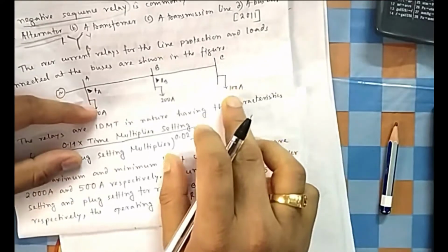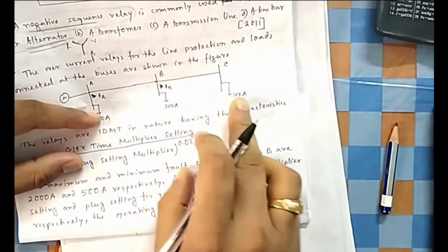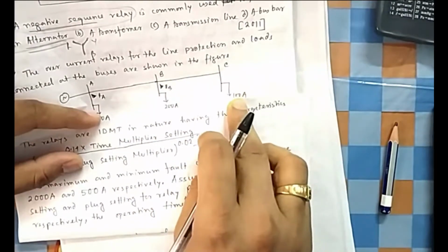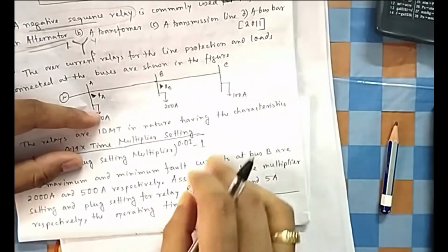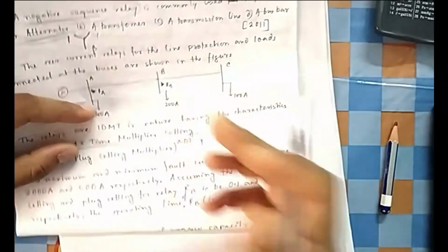Normally in that problem, you will see in the link that I have provided, the CT ratio is chosen by taking some overload. If it is 100, then generally we take 25% overload, so 125:5 would be the good choice. But as they have not mentioned anything about overloading in the question, we will take 100:5 only.